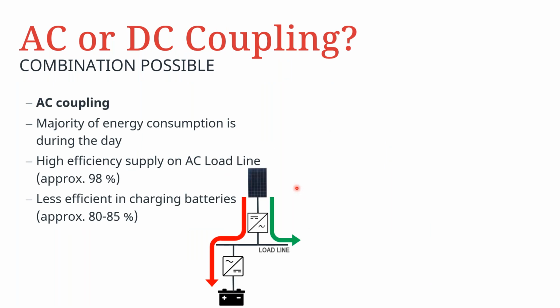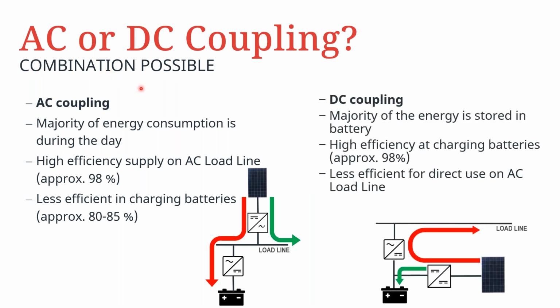So the choice is whether you are doing AC or DC coupling, but like we have said, you can do a combination of both. Here is just to differentiate what each of these means. An AC coupled setup is ideal when the majority of the energy consumption is happening during the day. Therefore, you have a very high efficiency of power conversion from DC to AC, which can be above 98% for Fronius inverters. The downside of this setup is the battery charging, where you have slightly lower efficiency.